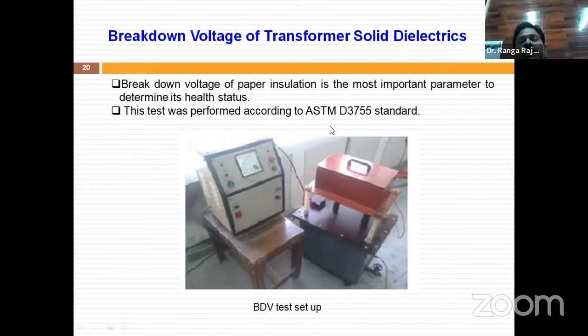The standard describes the test procedure in detail and also gives reference values, such as the breakdown voltage for a fresh sample as well as aged samples. We compare our result with the fresh sample values in the table to see how much deviation there is. Based on the deviation, as a condition monitoring expert, we should decide whether the paper needs replacement, whether the transformer needs shutdown, or if it is still good, how many more days it will work — we also have to predict the remaining life.